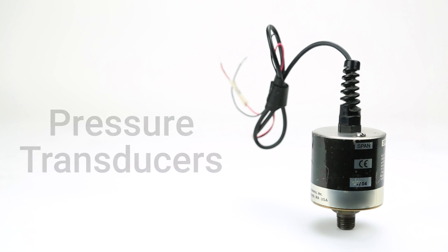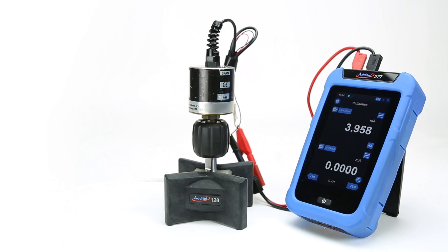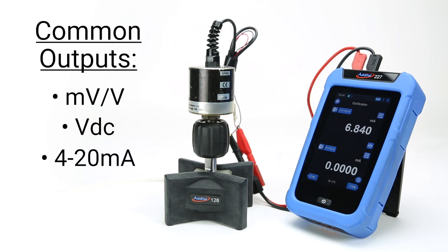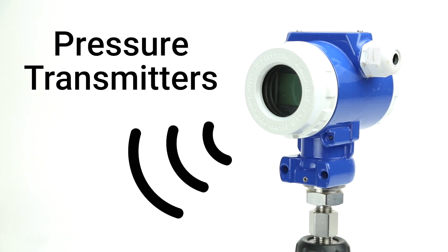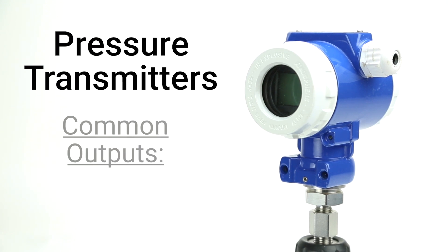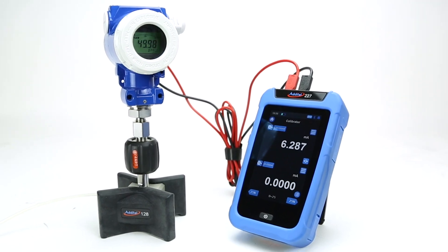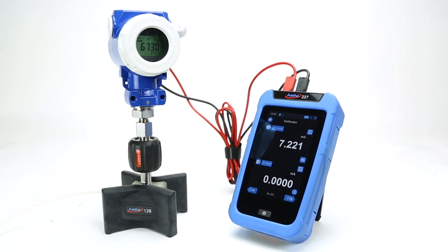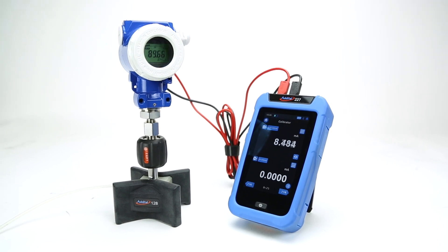Similar to modules, pressure transducers convert a pressure reading into an electrical signal, but unlike modules, the output can be measured and recorded by most types of electrical readouts. This electrical signal will typically be in millivolts per volt and will require a physical connection. Pressure transmitters are almost identical to transducers, but they also amplify and send their signals to a receiver, most commonly in the form of volts or a 4 to 20 milliamp signal. In general, transmitters are preferred when sending a signal over longer distances, due to being the least affected by electrical noise and resistance found in signal wires.